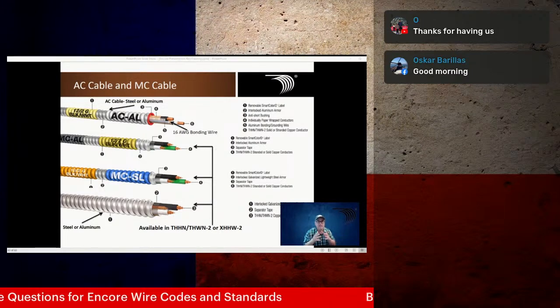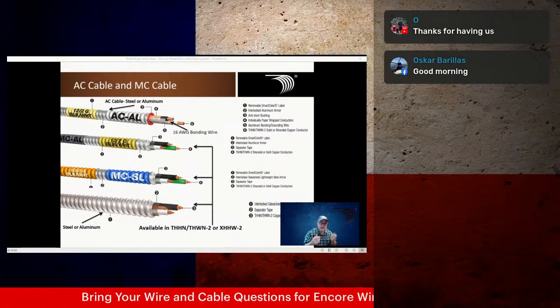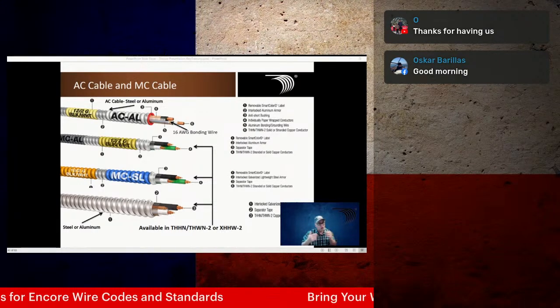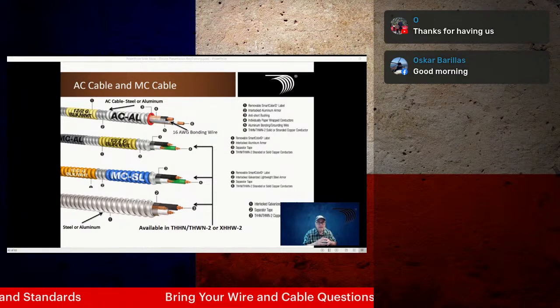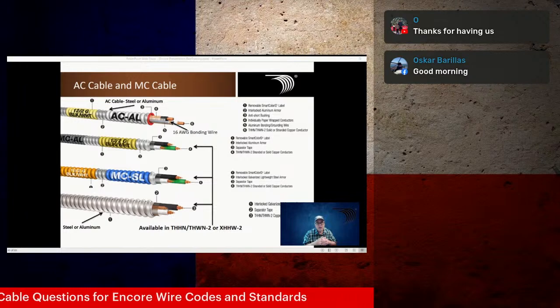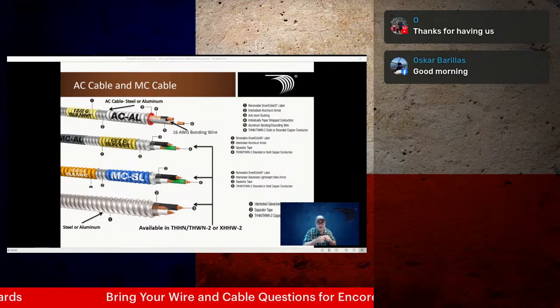And if you look at it, you can tell that if it has a yellow label, those are 12 gauge inside, okay? And if it has a white label, there'd be 14. If it had an orange label, they'd be 10. That's what you see visually by our Smart Color ID system. And I'll remind you that they can be ripped off. All you have to do is grab them and take them off.